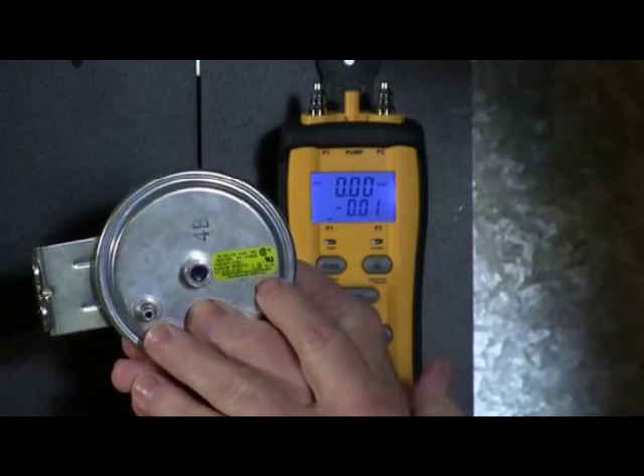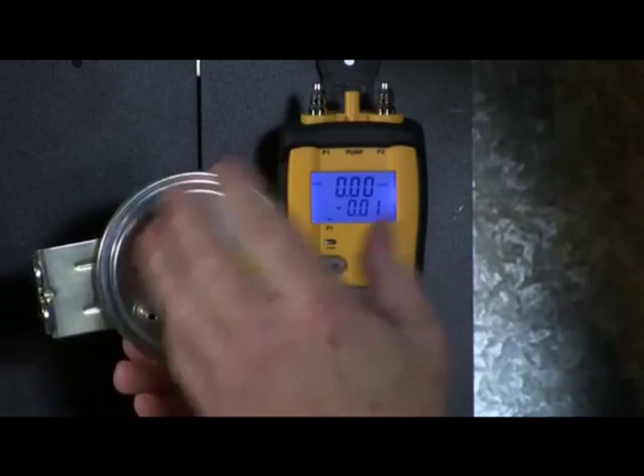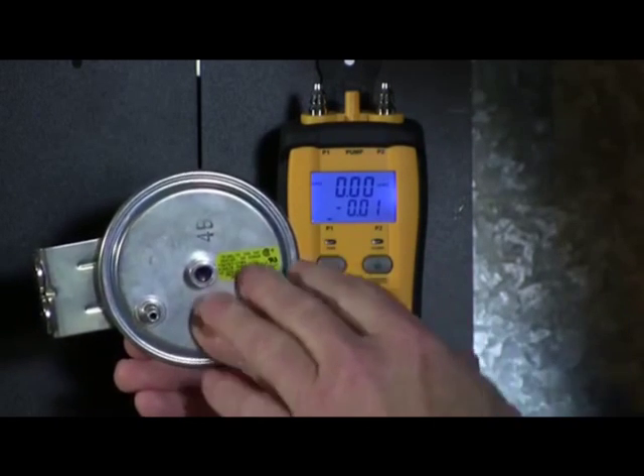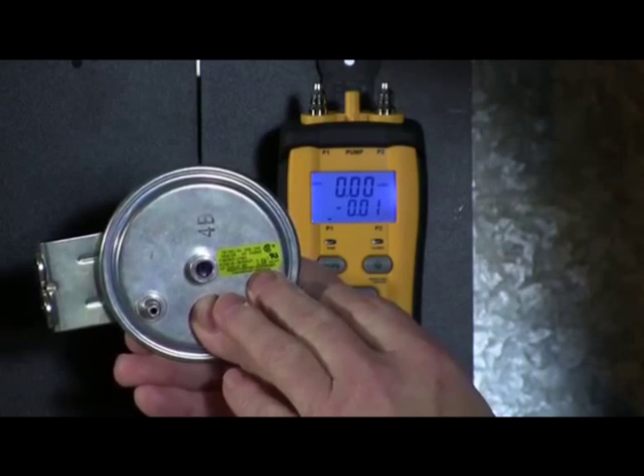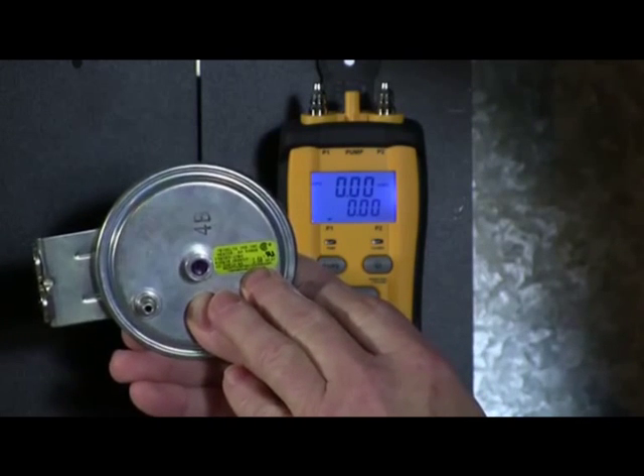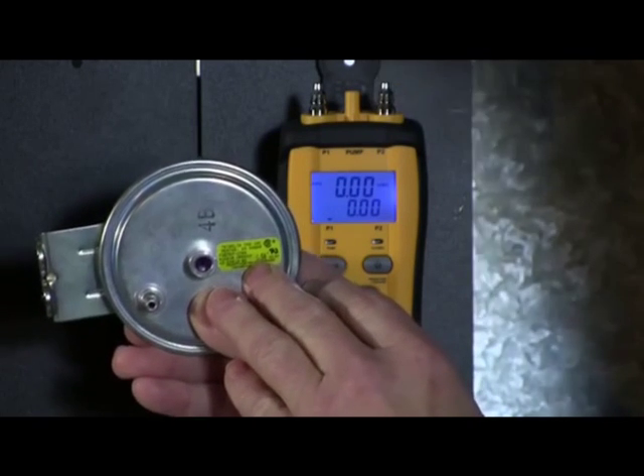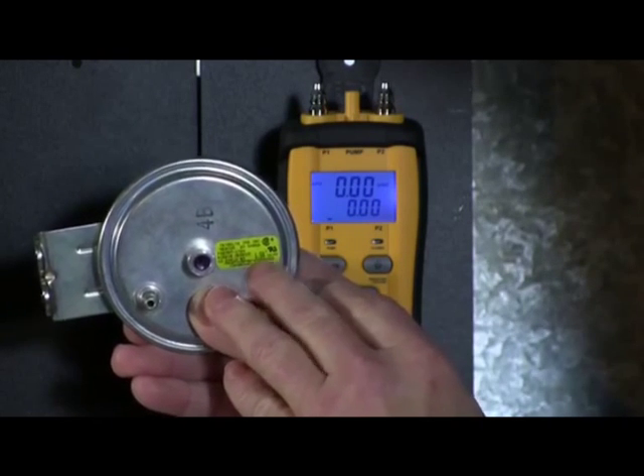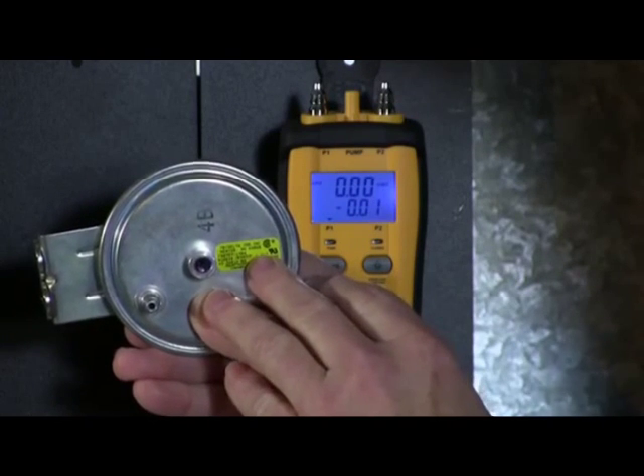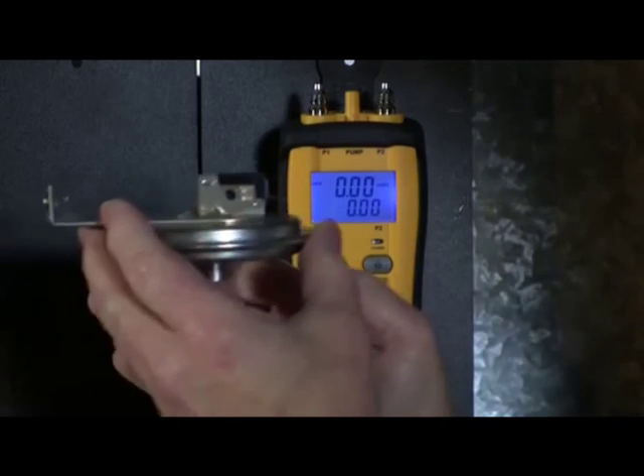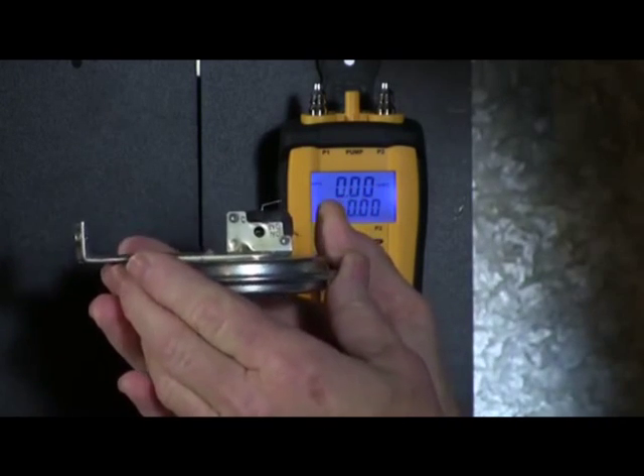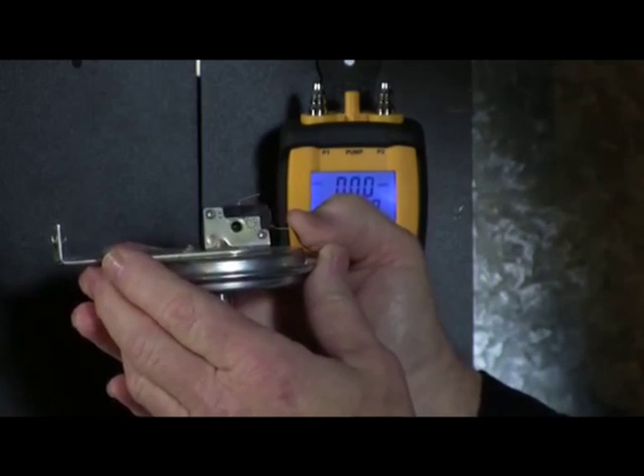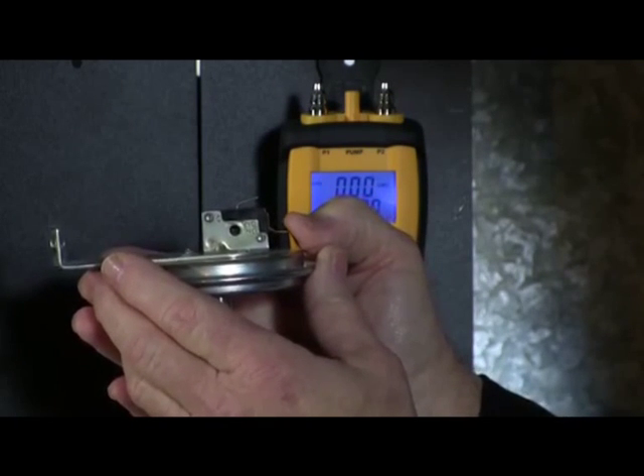On this particular switch, you'll see it only has two terminals. It has a common and a normally open. Those are the terminals that you would use to test the switch. Some switches have a third terminal, and in that case that would be a normally closed. You do not want to use that, even on a three terminal switch. You would just use the common and normally open.